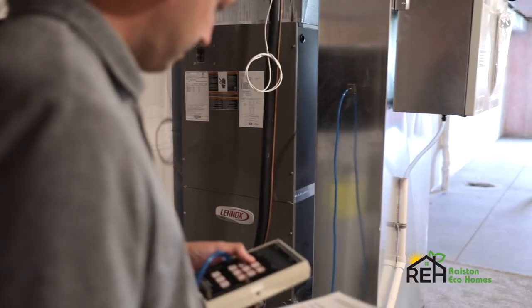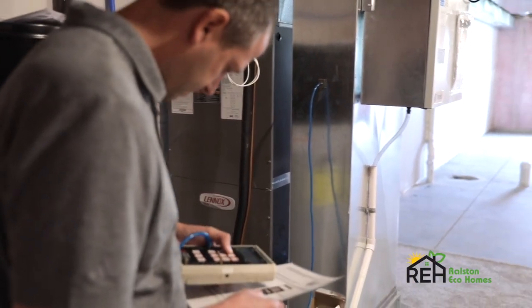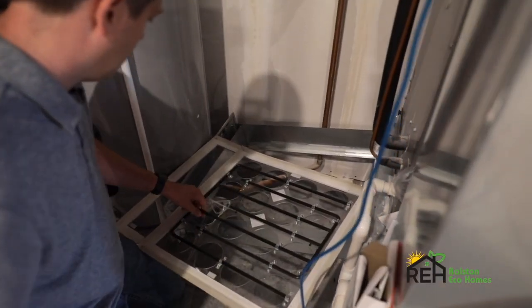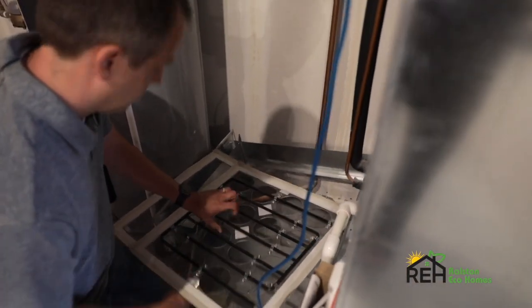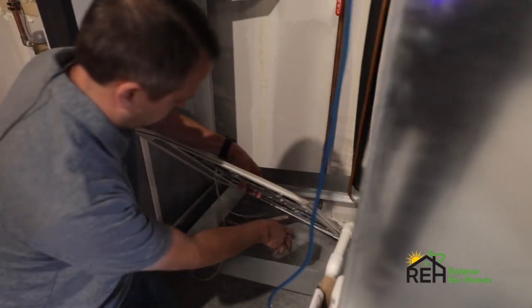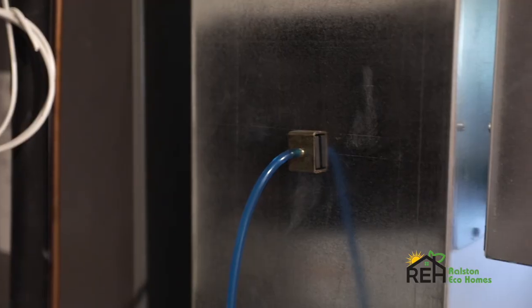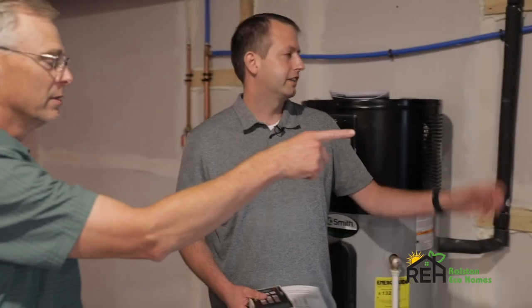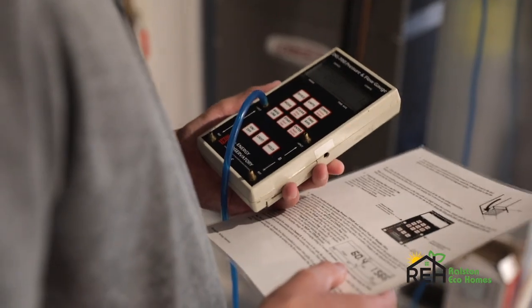So Adam, just explain to me what you've done here, because you've drilled some holes in my system. So we have a hole here. Yeah, so this is going to take a static pressure measurement. Okay. It's going to give us a baseline for using our flow grid, which is a tool that goes into the filter rack. Okay. And it measures the actual air through the system as it's operating. All right, so this tube that's going into that, this is the return here. Correct, yep. Okay, you're going to be able to measure that flow.